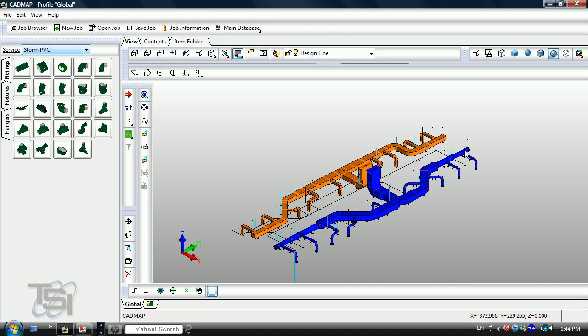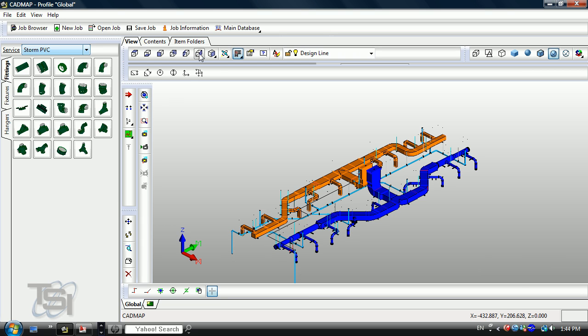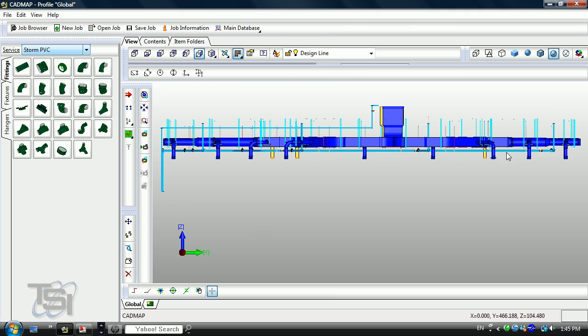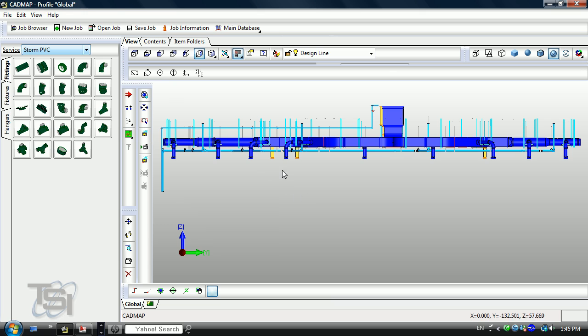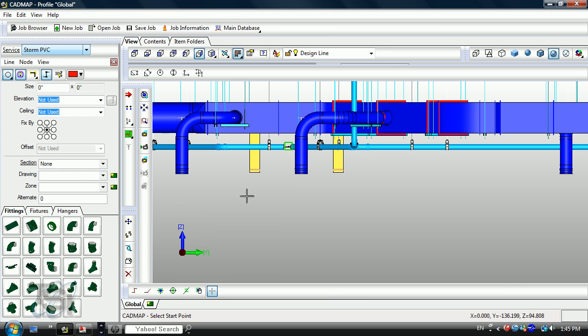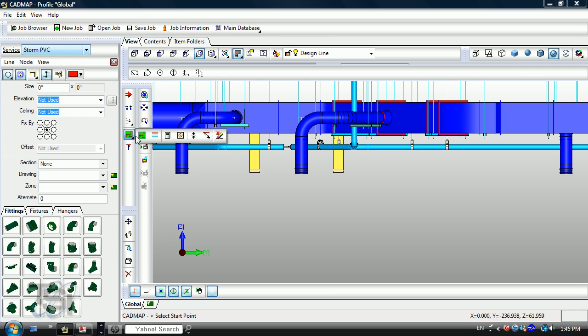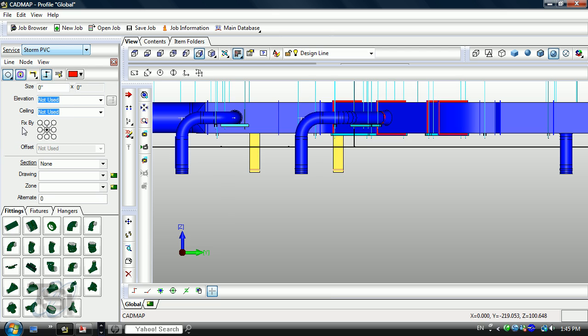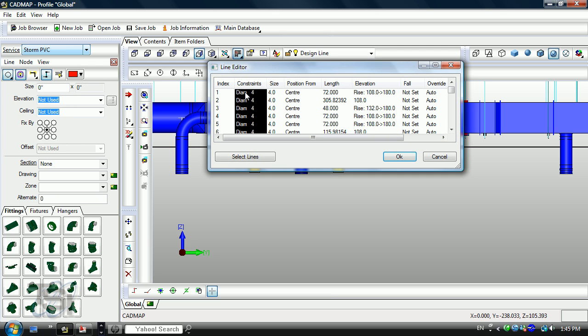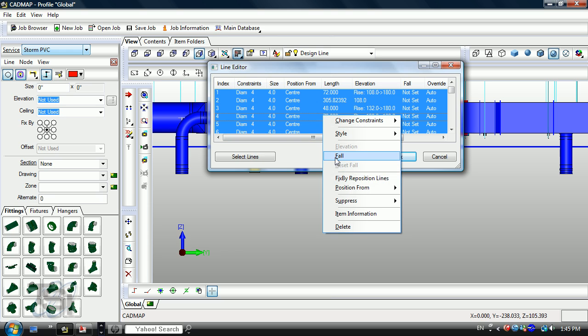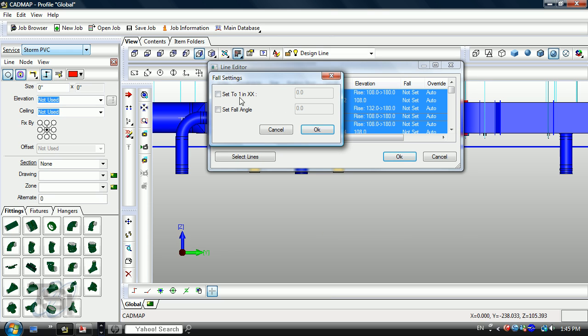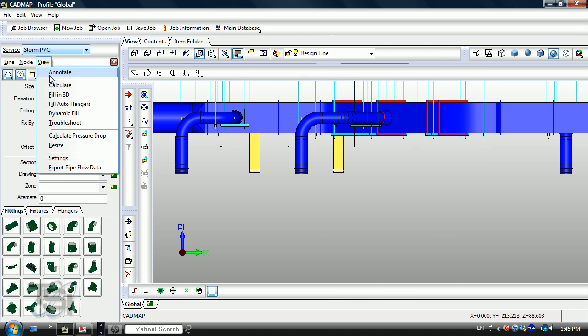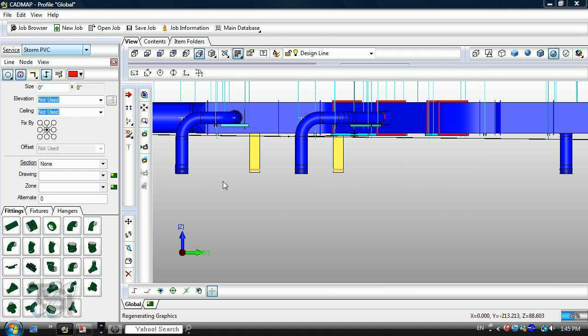You'll see it right here. On the plumbing I'll pull in the storm drain. As I pull this in, this is going to be a flat system right here. So what I'd really like to do is go ahead and define that to be a slope system. If I go ahead and put that in the side view here you can see it's just flat. So what I'll do is go ahead and modify that system by making this DesignLine active. I'll just take off those piping materials. I'll go to edit, use a windows selection set to grab those components, and I'm going to right click and go to fall.